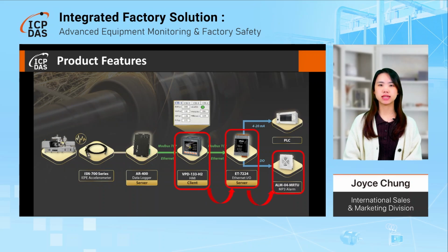If an alarm is needed, the VPD module sends a signal to the ET7224 Ethernet I/O module via the Modbus TCP protocol. The DO channel of the ET7224 then activates the ALM series MP3 alert module. Additionally, the VPD module uses the ET7224 Ethernet I/O module to output the current values to the PLC, allowing the PLC to monitor the machine's vibration status in real time.